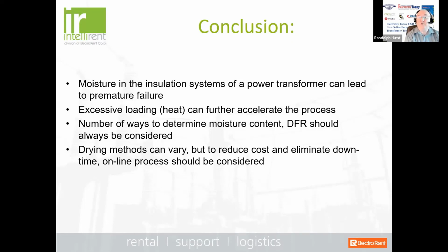If it works, could it be that the problem was not solved but shifted to another time on site? Yes, especially when you start putting a load on a transformer, and a continuous load. Sometimes the problem with a factory acceptance test is if you use a large load bank to simulate load, it's only there for a certain period of time. And this was the problem that we saw at the utility with the aux transformer.